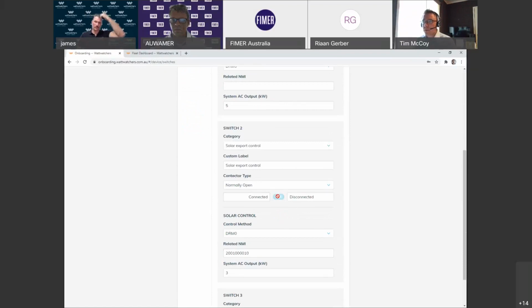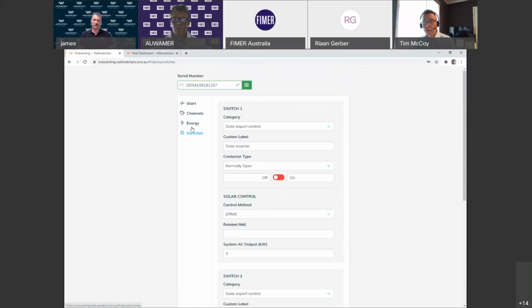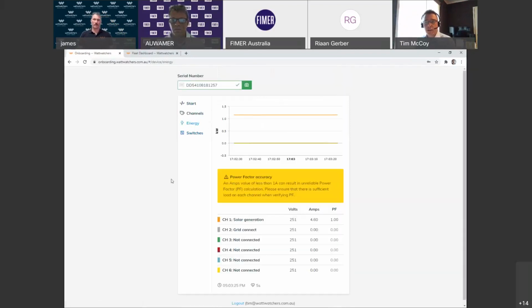So we'll simply flick the switch. That signal will now take around 5 to 10 seconds to go from the system down to the auditor. It immediately switches the contactor, and the DRM port on the inverter should respond within about 60 seconds, usually within 10 to 20 seconds. And we should see this solar ramp down from that 1.1 kilowatts.